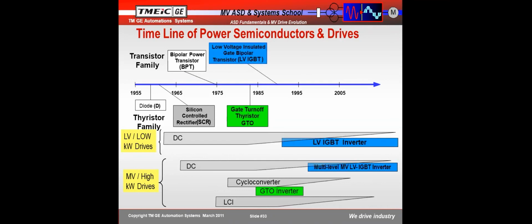Now, the IGBT came out in about 1987, was in drives about 1988, developed by the Japanese. It's called an insulated gate bipolar transistor, and for the first time, we could turn these things on and off with very, very low amounts of voltage and current. So on that gate, we could turn this on very easily, and that got rid of a lot of circuitry in drives, made them far more reliable, and the IGBT revolutionized low voltage drives, but not available in medium voltage.